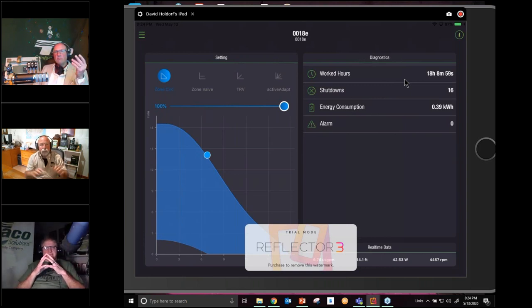So we've got the moose antlers. We've got five zone valves supplying and five dedicated returns coming back. All I'm trying to do is get an idea of what the actual system resistance is. That's why we open up all the zones manually. We turn it all the way up to 100%, and we just see where it settles out. What I would recommend you do at that point is it gives you an idea.